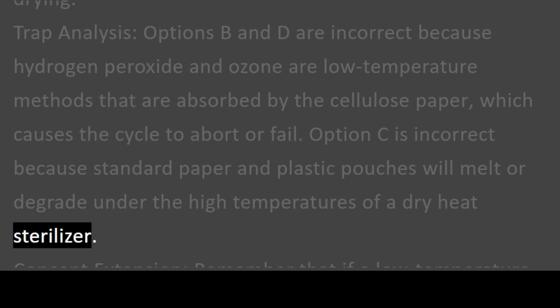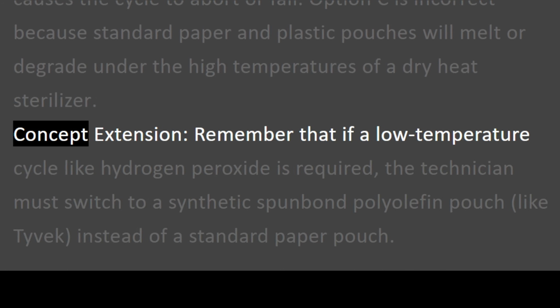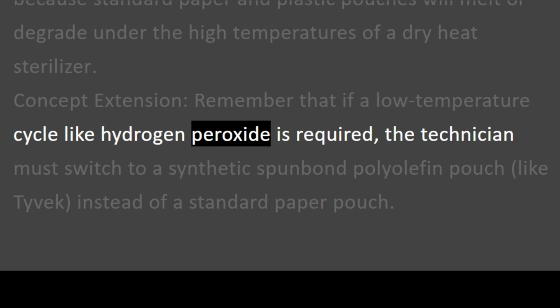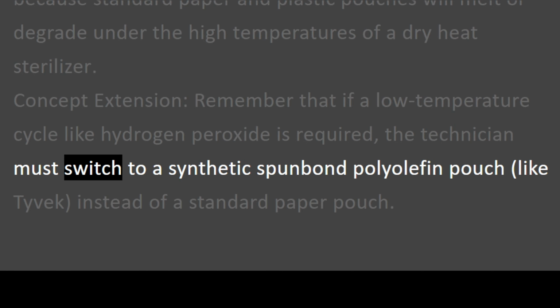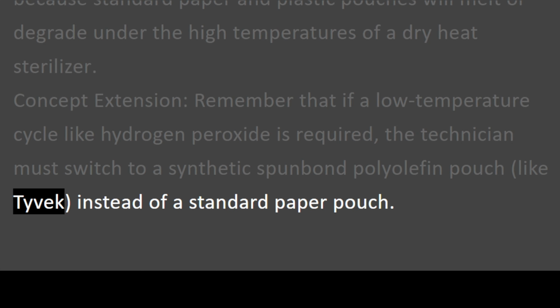Option C is incorrect because standard paper and plastic pouches will melt or degrade under the high temperatures of a dry heat sterilizer. Concept extension. Remember that if a low-temperature cycle like hydrogen peroxide is required, the technician must switch to a synthetic spunbond polyolefin pouch, like Tyvek, instead of a standard paper pouch.